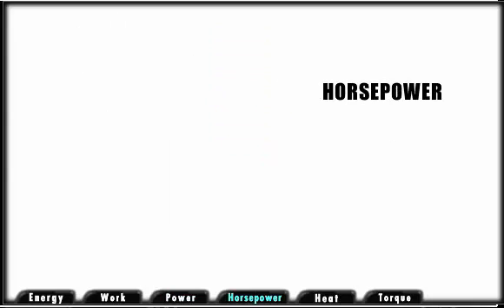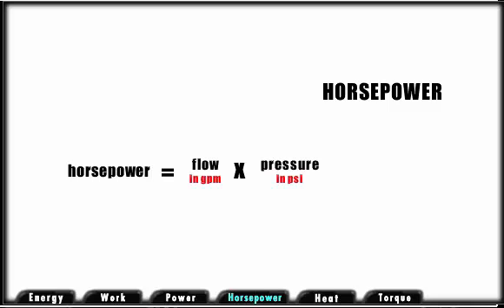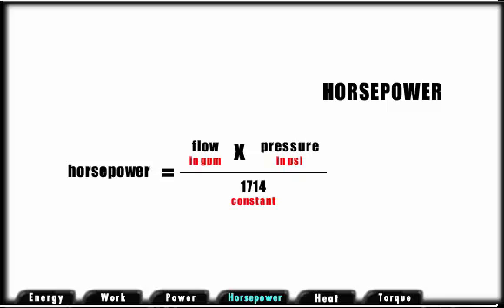Mathematically, hydraulic horsepower is expressed as follows. Horsepower equals flow in gallons per minute times pressure in pounds per square inch divided by 1,714, a constant.